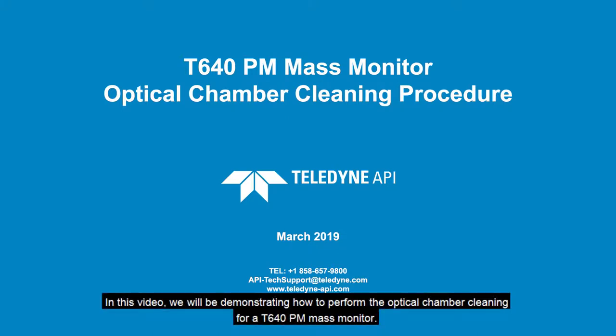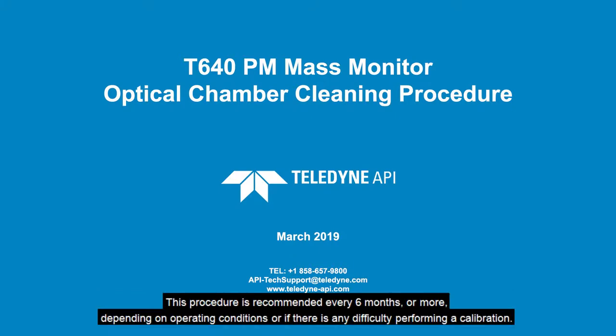In this video, we will be demonstrating how to perform the optical chamber cleaning for a T640 PM mass monitor. This procedure is recommended every six months or more, depending on operating conditions, or if there is any difficulty performing a calibration.